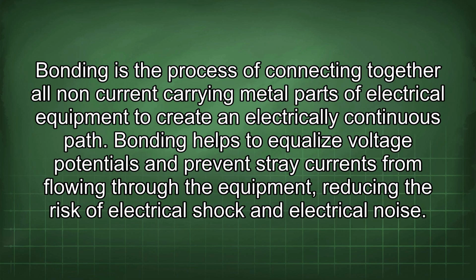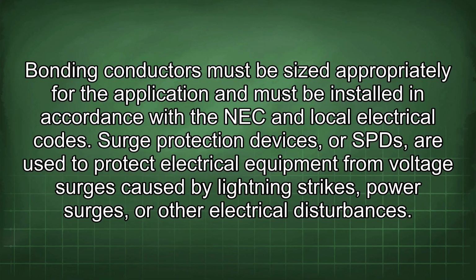Bonding is the process of connecting together all non-current carrying metal parts of electrical equipment to create an electrically continuous path. Bonding helps to equalize voltage potentials and prevent stray currents from flowing through the equipment, reducing the risk of electrical shock and electrical noise.